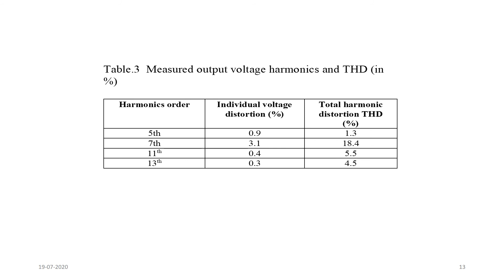For the 11th harmonic also, the voltage is okay, 0.4, but the current slightly exceeds 5%, at 5.5. But when you go to the higher order, the 13th, we get values under the standard, that is 0.3 and 4.5. So what is the conclusion? The 7th order harmonic exceeds the IEEE standard value, that is 18.4 on the current harmonic side, even though the voltage harmonic is under 5%. This is what we observed from our laboratory part, where we developed a small-scale prototype model and got the THD values for different orders.